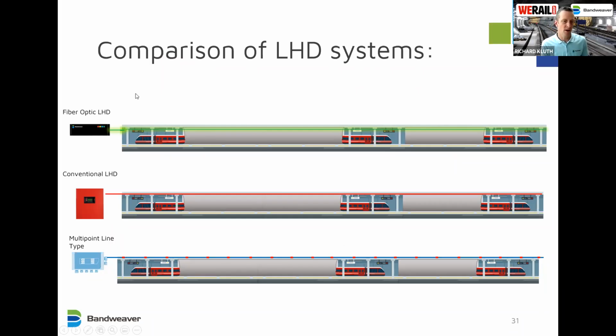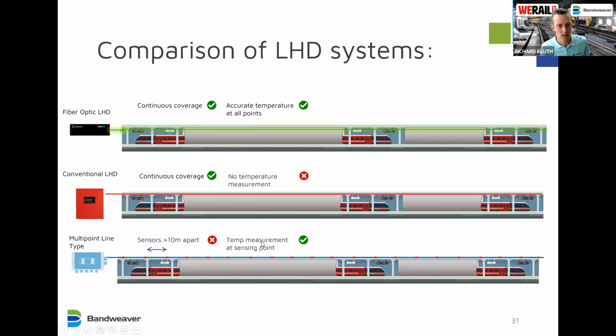tunnel. So first point to note, they're all installed, broadly speaking, in a similar way. They're attached at the roof or the wall in the tunnel. For this example, the ceiling. The first 2, the fiber optic and the conventional, have continuous coverage. You have coverage everywhere in the tunnel. The multi-point only where the sensors are. And as we said earlier, they can be more than 10 meters apart.